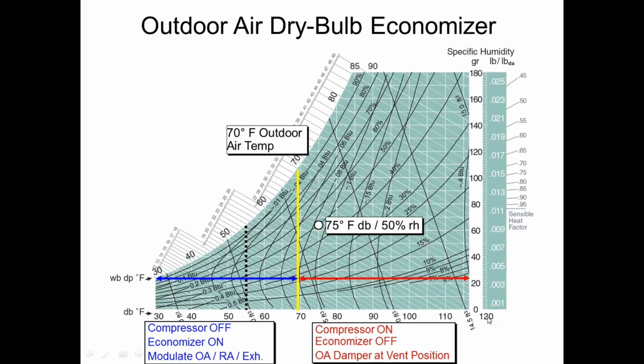For you guys that love psych charts, which I'm sure everybody loves psych charts, and it wouldn't really be a PE meeting if we didn't have one. So you guys know temperatures along the bottom axis, absolute humidity is at the vertical axis, the relative humidity are the curved lines, 50%, 60, 70%, and so on. You guys know the drill. With the old economizer, historic set point of being 55 degree changeover point, that's that dotted black line. Now my new changeover point is basically 70 degrees, right over here on the yellow line. So if it's below 70 degrees, I am in economizer mode. If it's above 70, I am in compression mode where the red line is. All right.